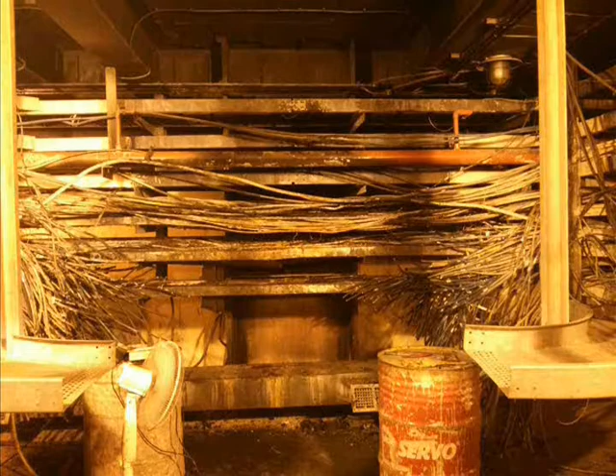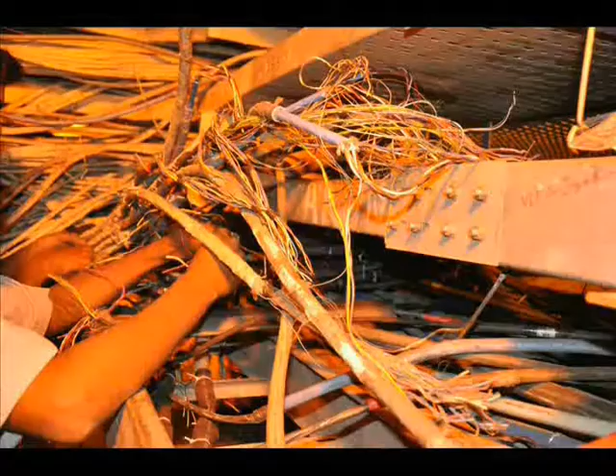The batch process involved cutting and tagging all the cables in a particular tray individually, followed by cable segregation and sleeving. It was planned to divert half of the cables to the new tray and retain the other half in the older one, so that simultaneously two cables at both ends could be joined.